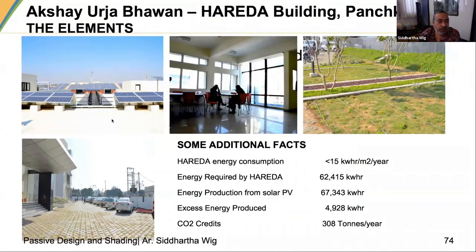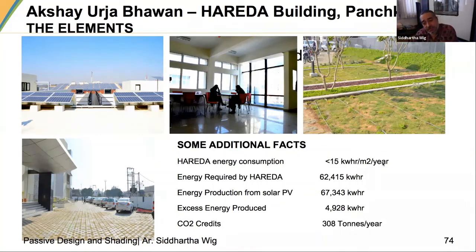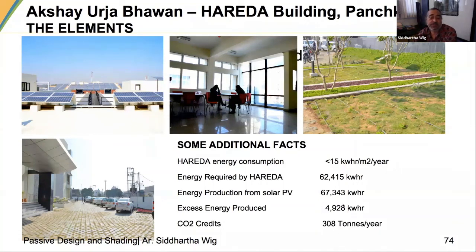You can see the roof — very reflective with a high albedo — along with the solar power panels. There was also a 600-litre solar water heater for all dormitories and guest rooms. There was complete natural light in the canteen area. A two-pass water system was used — all washing water was cleaned in a gray water recycling unit and reused via drip irrigation. Simulation results showed 15 kWh per square meter per year; post-occupancy studies corroborated this at about 13.7 kWh per square meter per year.